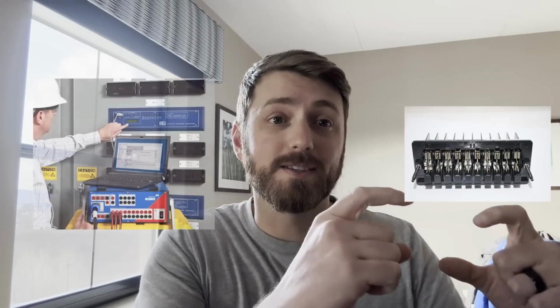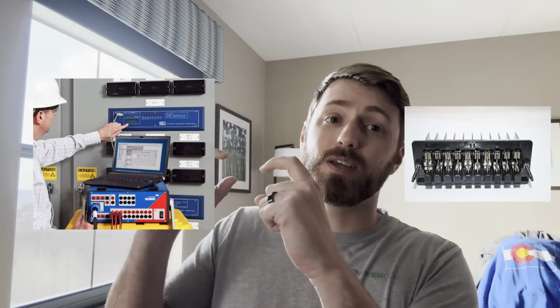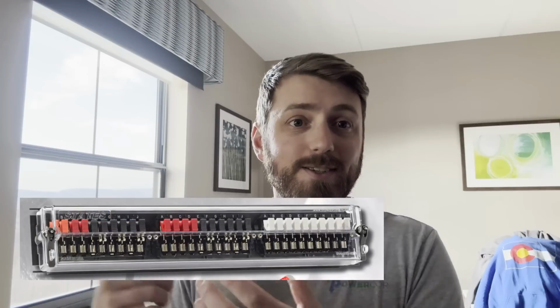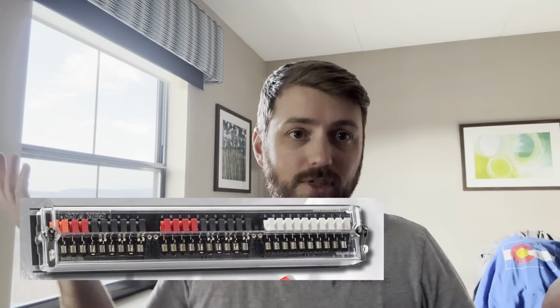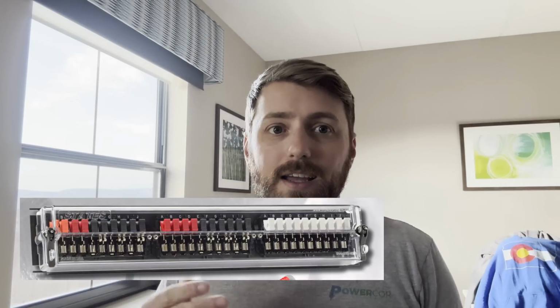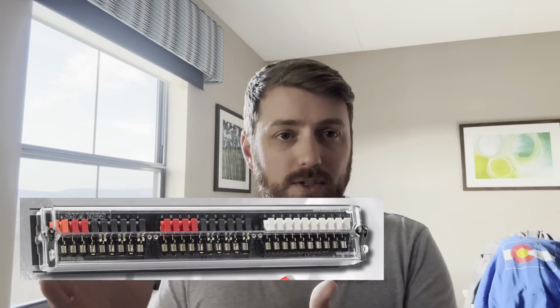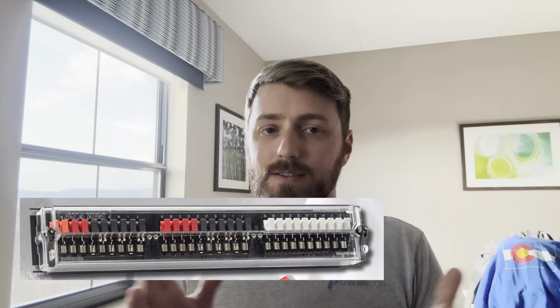Instead of reinventing the wheel, we took the same exact switch mechanism from the FT case and put it on the door of the switchgear, or into a 19-inch rack mount for our substation. We used the same switches, the same mechanism, the same design, really the same wiring. It's just now a discrete component.